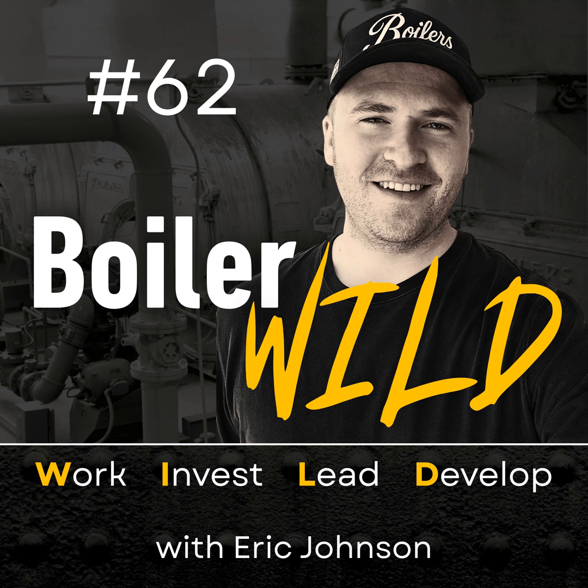So I cleaned everything up. I redid the positioning of the igniter. I re-gapped it, obviously gapped it properly, and fixed it. And that was a very frustrating series of days for the customer because nobody seemed to fix their boiler. But the only reason I fixed it correctly is, one, I was familiar with it, but even more, I took the time to open up the manual and understand what the igniter gap should be and where the igniter should be sparking. Just because the pilot lights doesn't mean that the igniter is sparking off the correct surface.